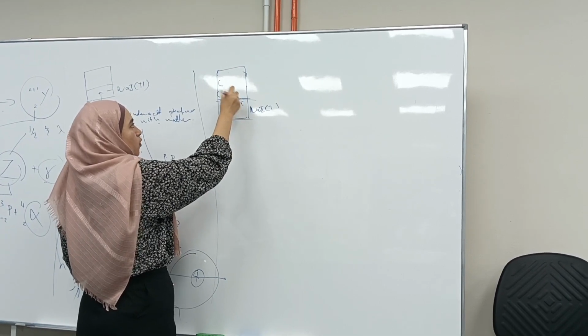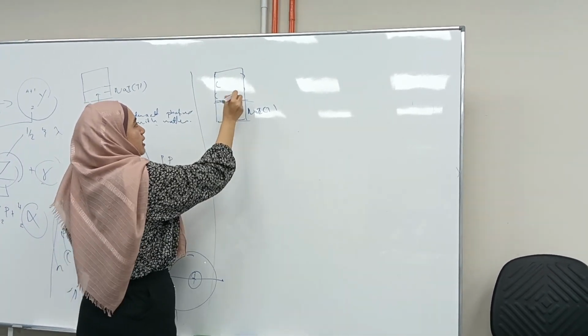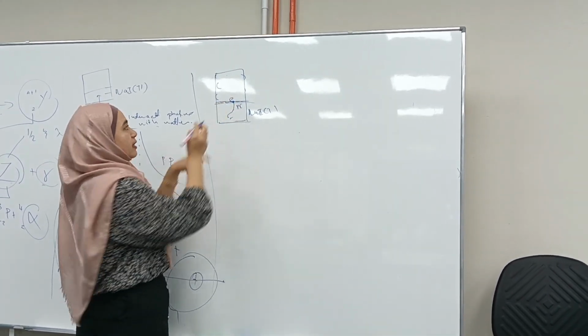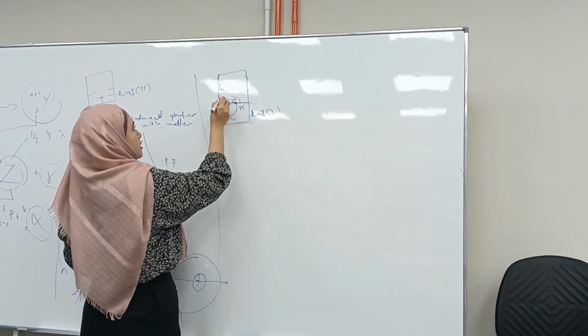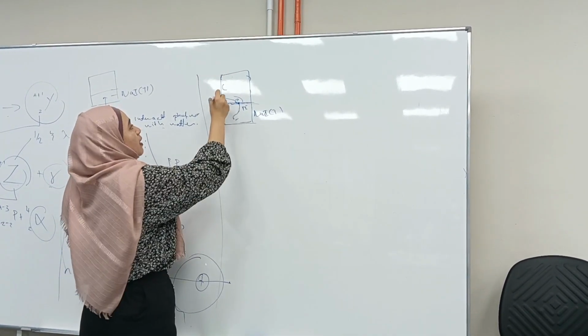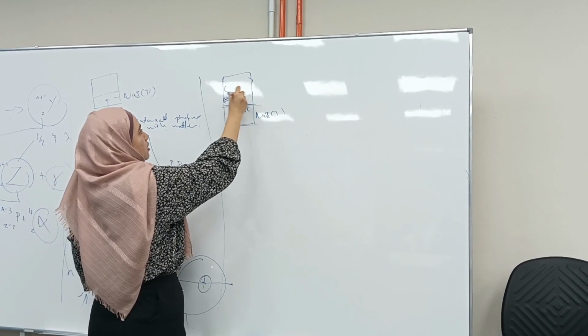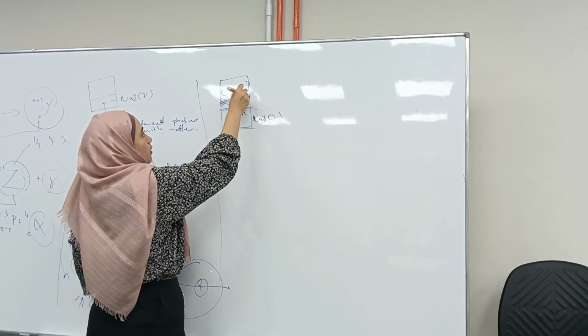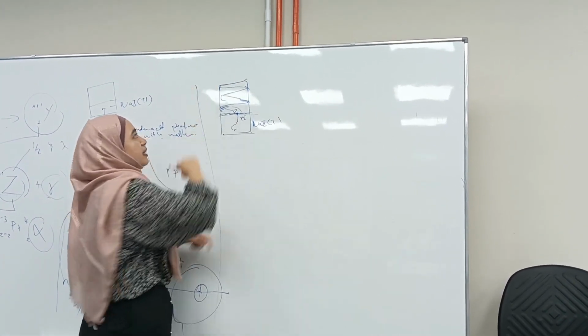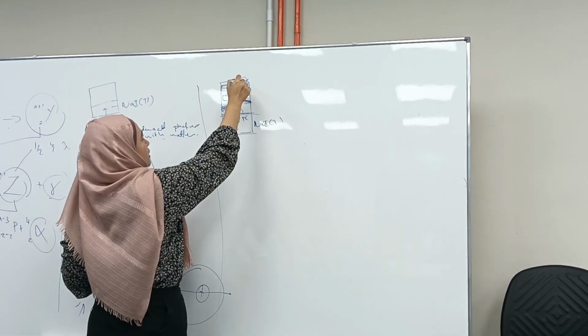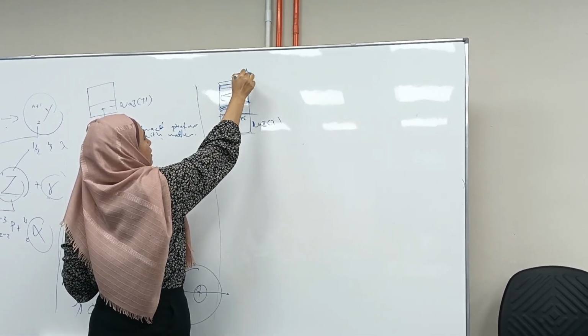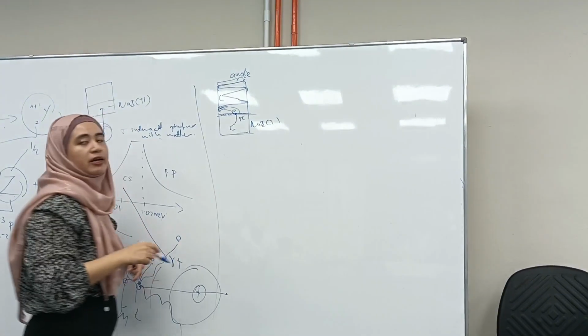The absorption of photons at the photocathode will emit one electron, and this electron will be focused up to this dynode to emit more electrons, and these will go to this side to emit more electrons. You can multiply this electron, and this information will be collected at the anode at the back of your sodium iodide crystal.